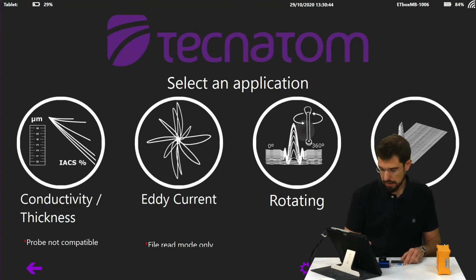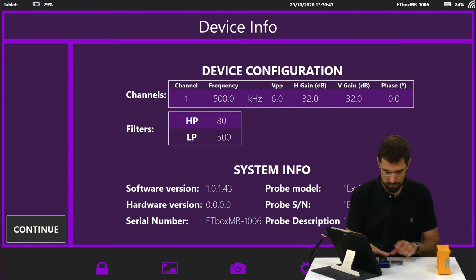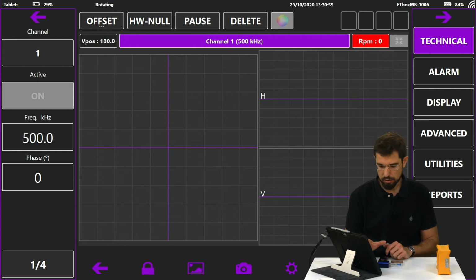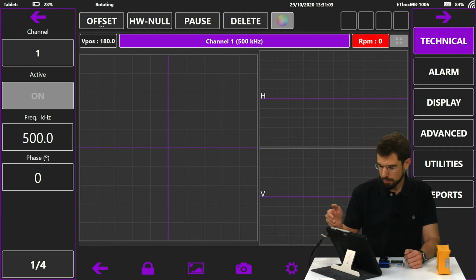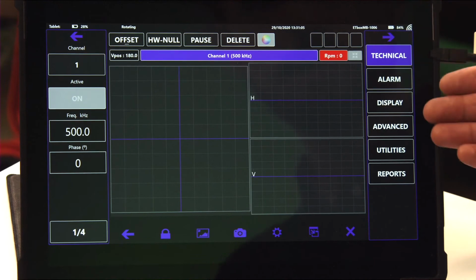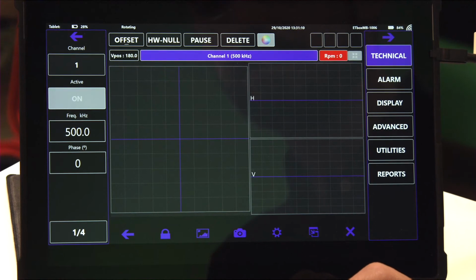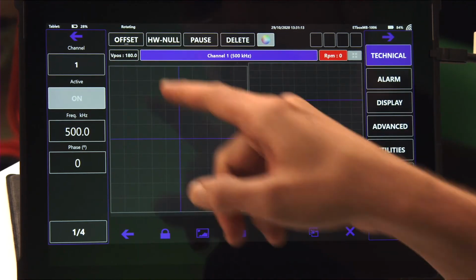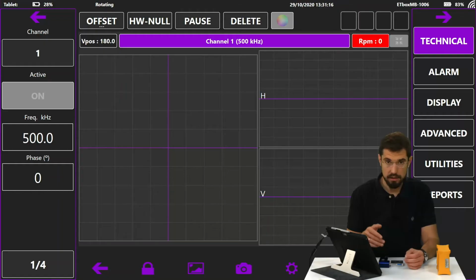Let's proceed with the rotary rotation application. We see that it loads. It has identified the probe. And we can access the application. This application is very similar to the conventional Eddy Current application. We can see we have the main menu with technical, alarm, display, and the rest of the tabs. Then we have a submenu on the left. We also have the same buttons at the top to modify the offset, gain, phase, do a hardware null, control the acquisition, and clear the buffer.